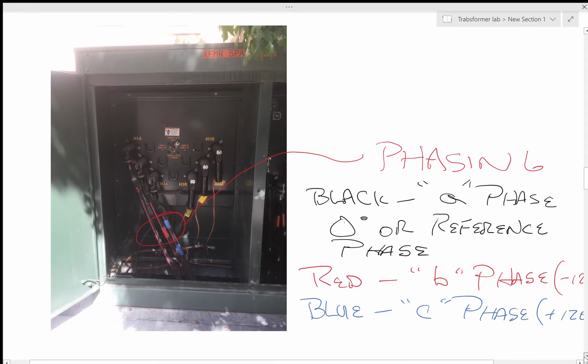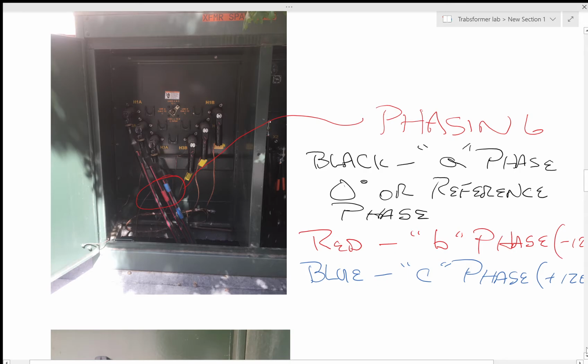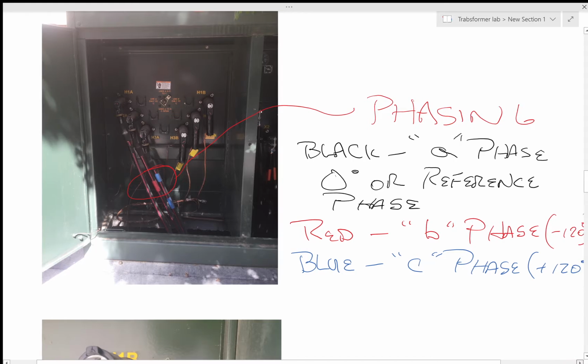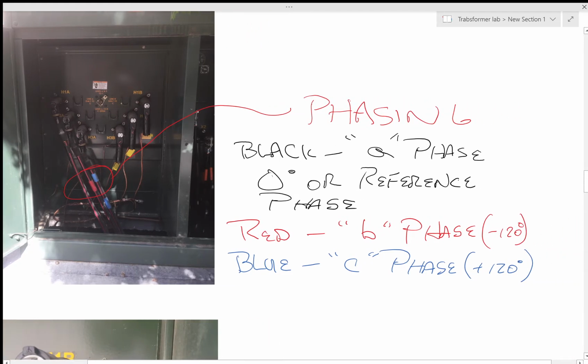So here's the high side of the cabinet. Notice the phasing. The black tape is the A phase or the 0 degree phase. The red phase is the B phase, and the blue phase is the C phase, which is plus 120 degrees from the A phase. Part of the problem is, really and truly, you don't know which one is the A phase, the B phase, and the C phase. All you know is that one's going to be close to 0, one phase is going to be close to minus 120, and one phase is going to be close to plus 120.